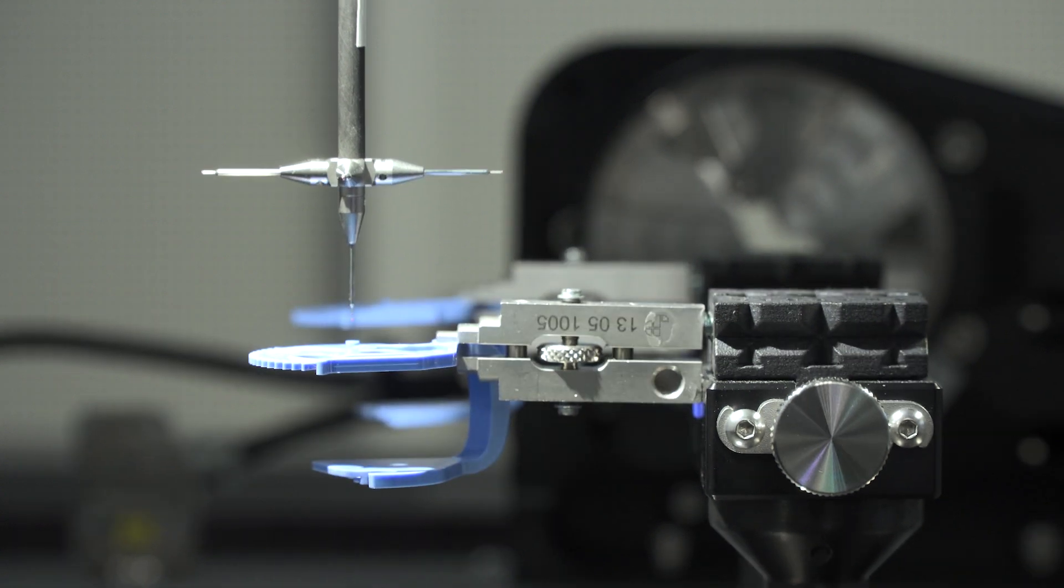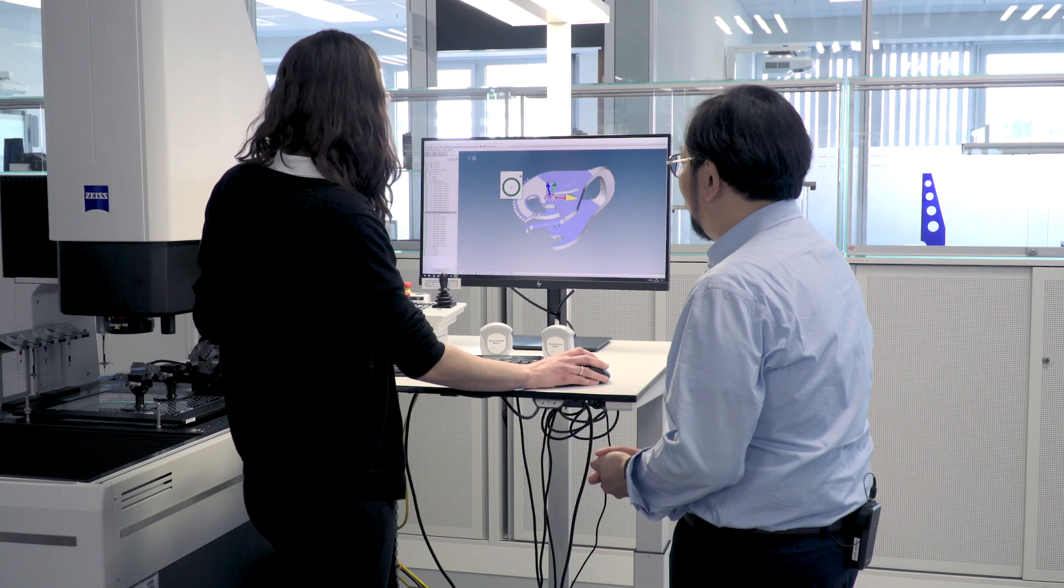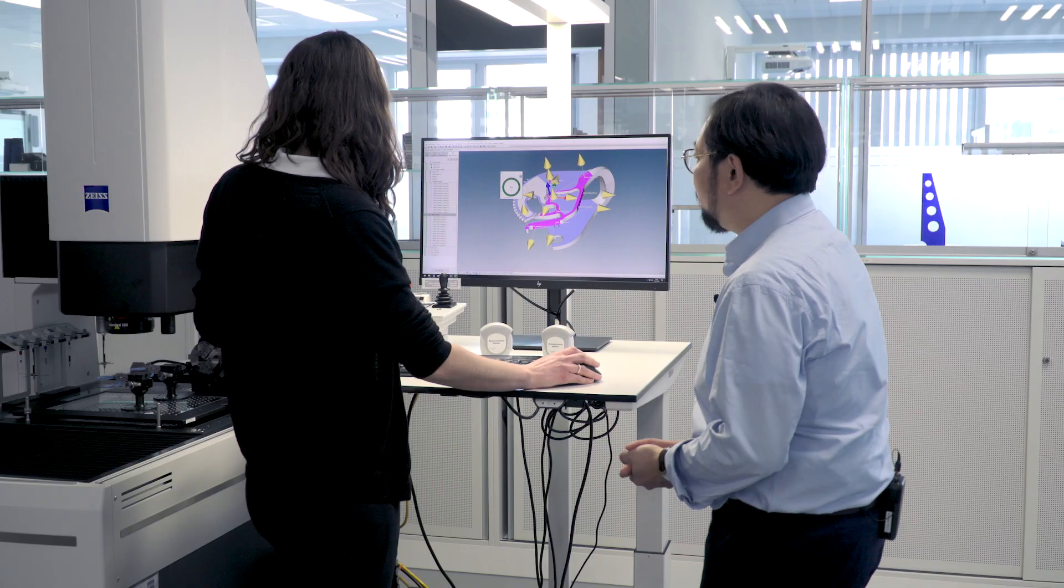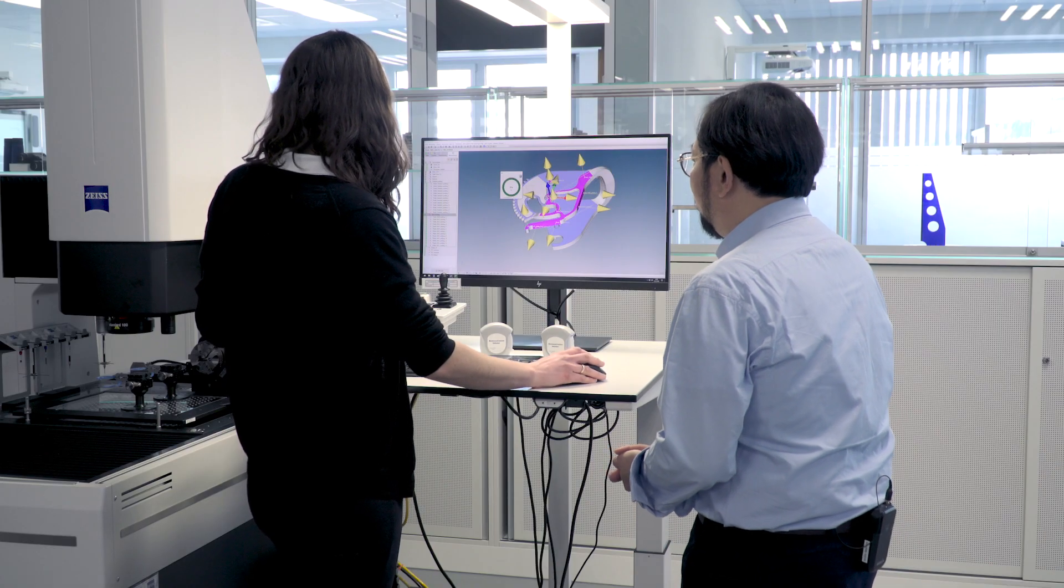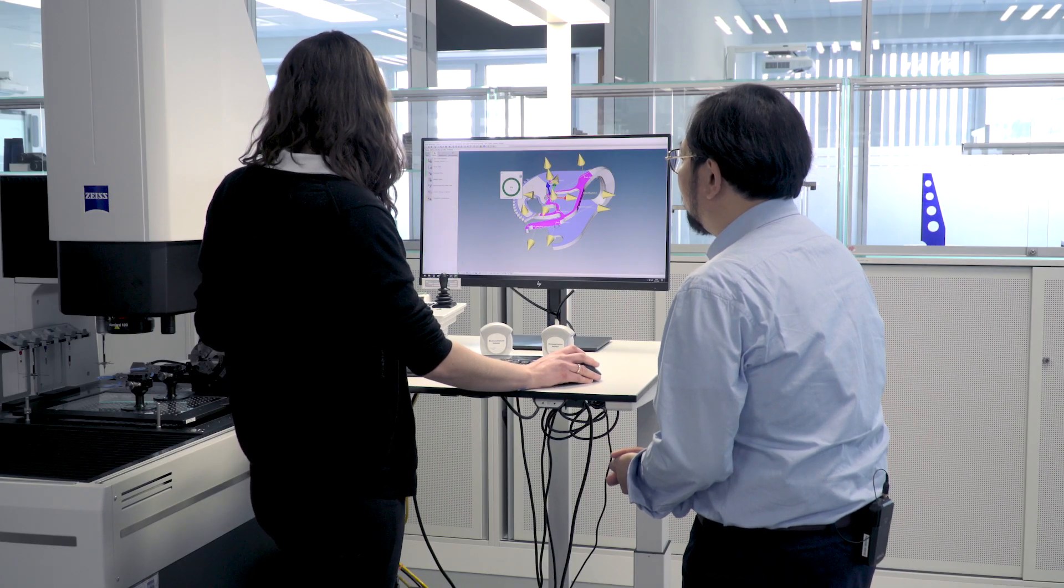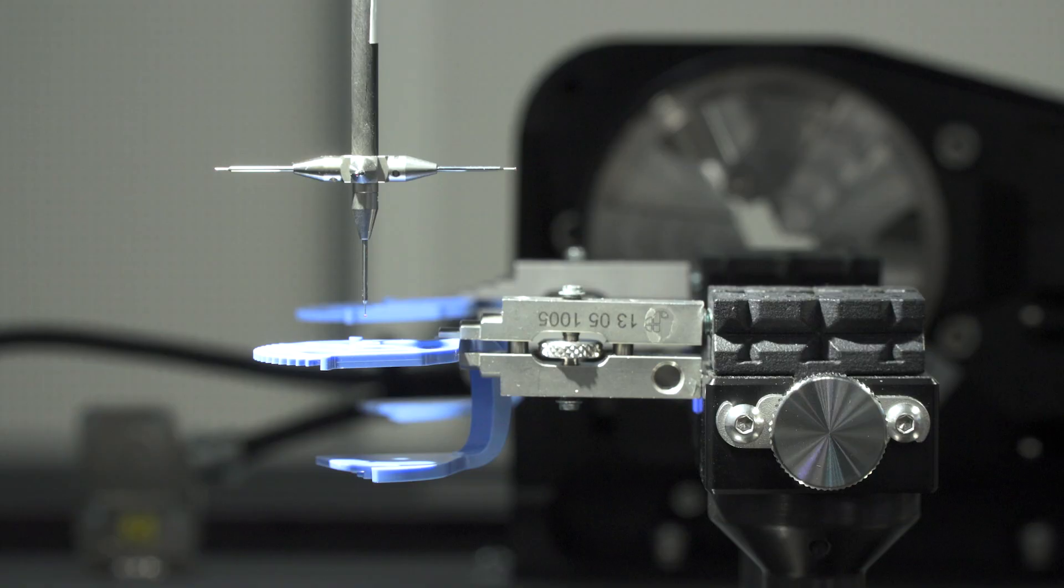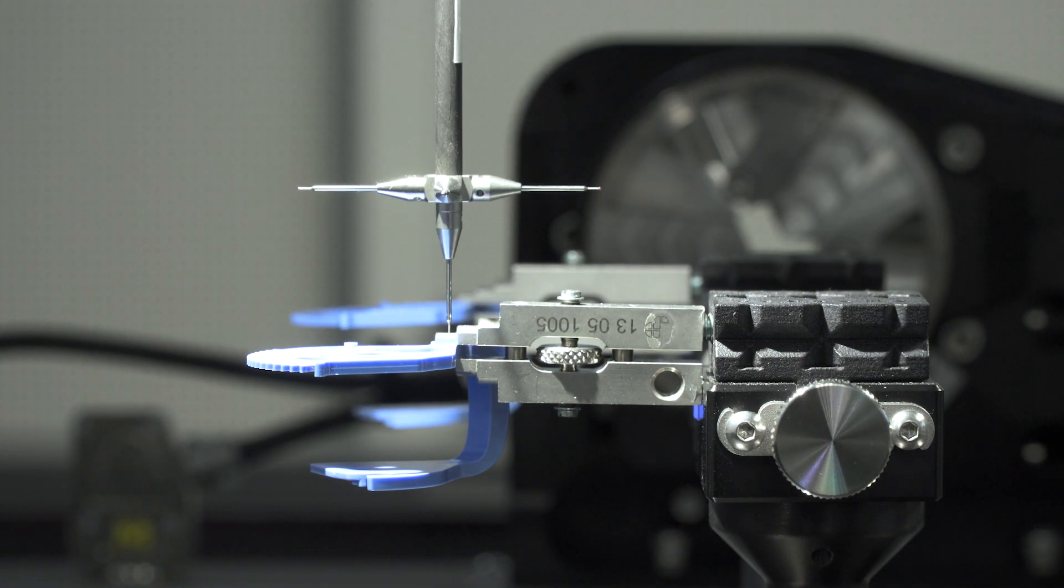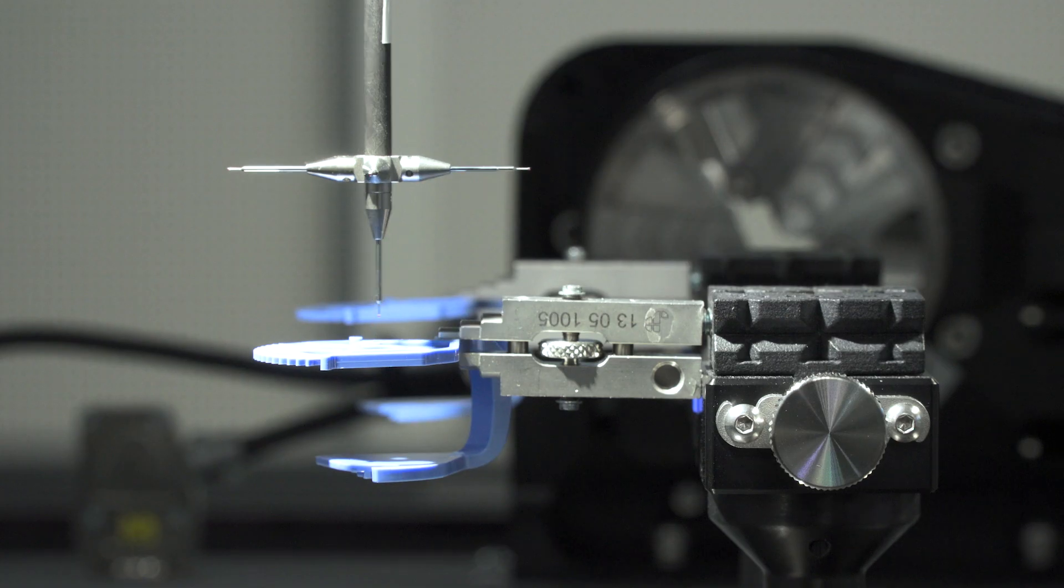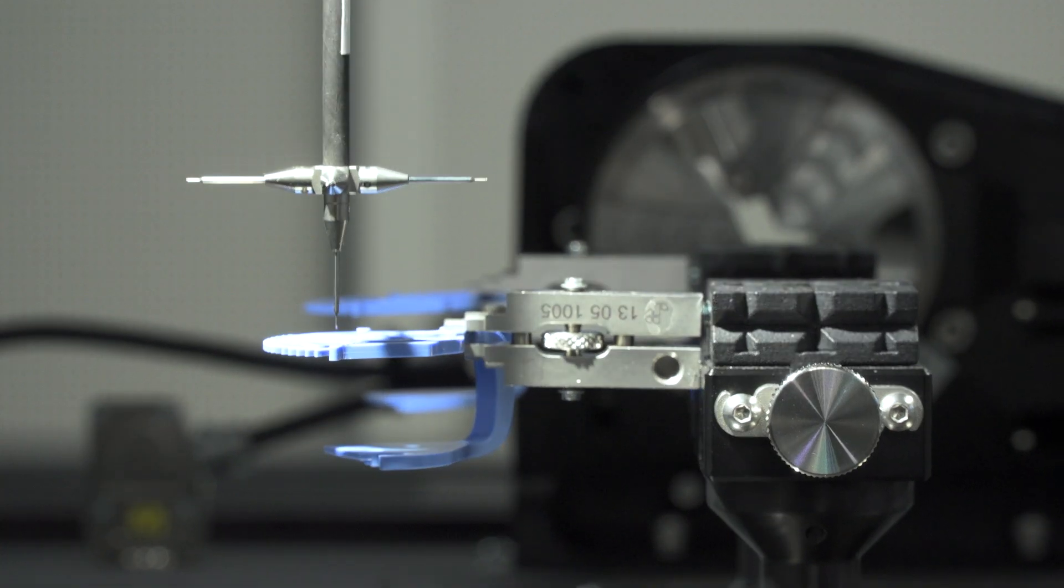So, it took around 31 seconds. Yeah. And now, I will activate the VAST probing mode. You can do that in measurement plan editor features on CMM parameters and probing parameter. And here, you can turn it on for each feature. Got it.